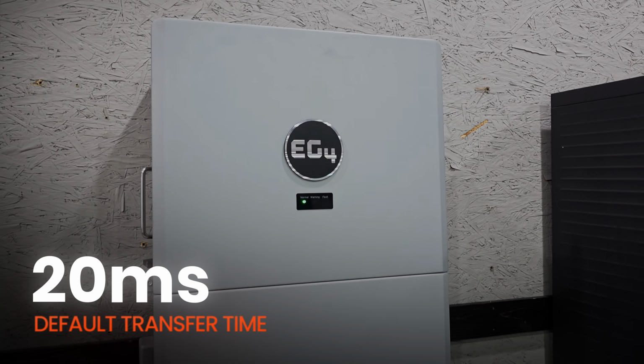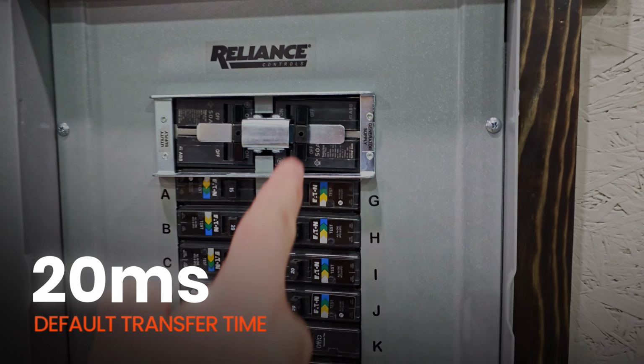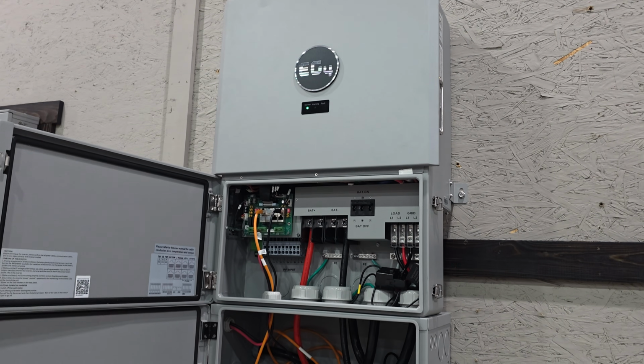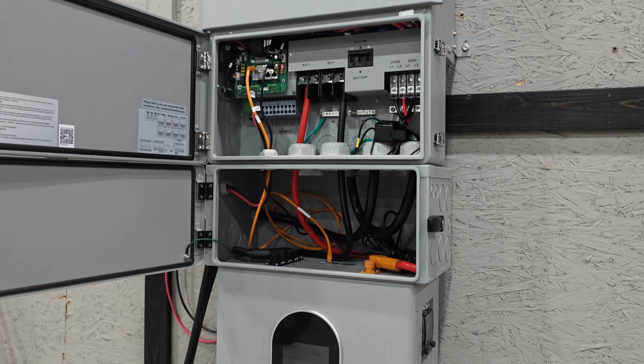The FlexBOSS 21 also has a transfer time of 20 milliseconds by default and 10 milliseconds when it's configured. Now, that is not the fastest transfer time in the world or on these inverters. For example, the Sol-Ark 18K is listed at 5 milliseconds. So if transfer speed is your top priority, this is something you need to compare carefully. But 10 to 20 milliseconds is still in a range that many people would consider acceptable for general backup loads. For sensitive electronics like computers, networking equipment, and medical devices, then you need to plan a little bit more carefully with those, because transfer time is not the only thing that matters.